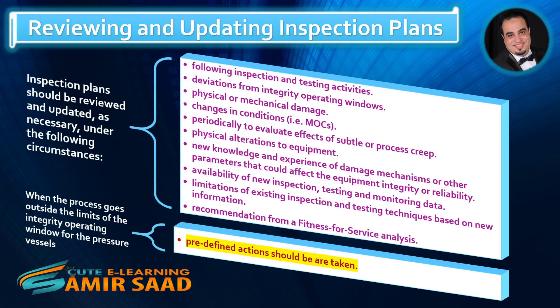Reviewing and updating inspection plans: inspection plans should be reviewed and updated, as necessary, under the following circumstances — following inspection and testing activities; deviations from integrity operating windows; physical or mechanical damage; changes in conditions; periodically to evaluate effects of subtle change or process creep; physical alterations to equipment; and new knowledge and experience of damage mechanisms or other parameters that could affect the equipment integrity or reliability.